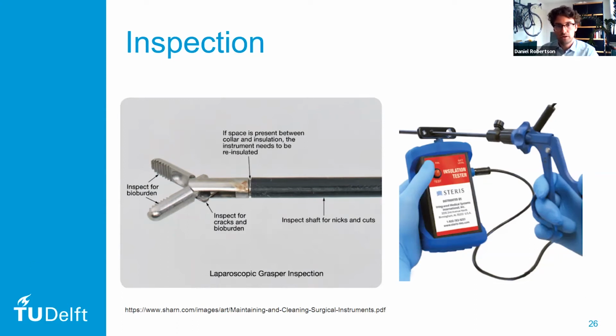Now, these damages in the insulation can often be very, very small. So they can be hairline cracks, they can be small holes, and a very good way of testing the insulation is with a simple device called an insulation tester. What this tester does, it runs on a 9-volt battery, and you connect the tester to the laparoscopic instrument, and you run it along the insulation. And when the insulation is damaged, it will give a sound. Now, instruments that have damaged insulation should either be re-insulated, which is a step you can get performed at certain companies, or they have to be discarded.